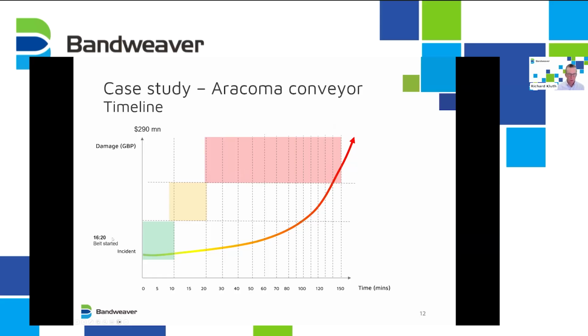So in here, the belt was started at 4:20. And then at 5:05 was the first smoke observed. So there's a sort of 45-minute window there where the fire started. We're not exactly sure when it was, but that's the first observation. 9 minutes later, the first CO2 sensor. 15 minutes after that, heavy smoke migrating into the primary escapeway. So this is potentially more than an hour after it, and still action hasn't been taken.